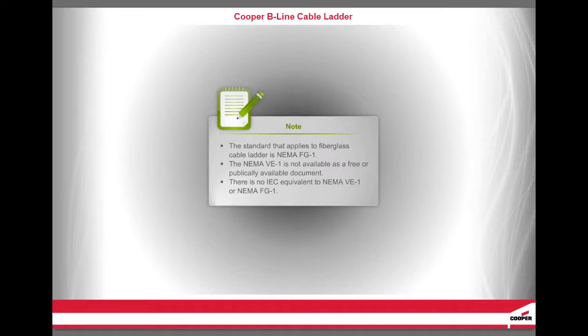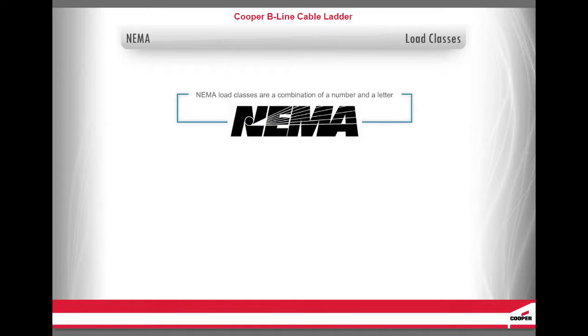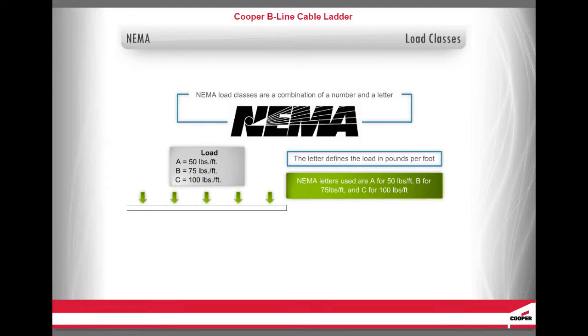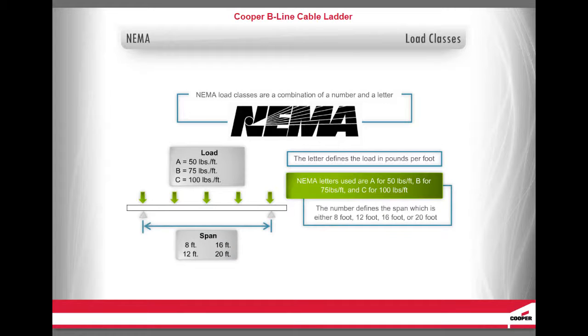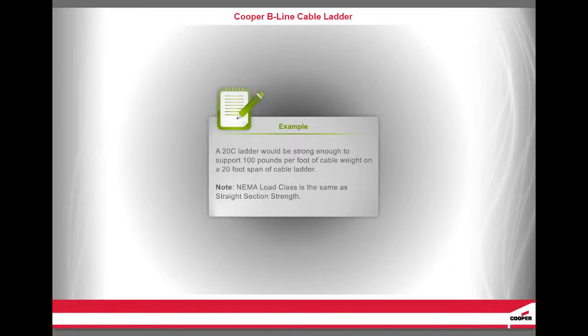The NEMA VE1 is not available as a free or publicly available document. There is no IEC equivalent to NEMA VE1 or NEMA FG-1. NEMA load classes are a combination of a number and a letter. The letter defines the load in pounds per foot: A for 50 pounds per foot, B for 75 pounds per foot, and C for 100 pounds per foot. The number defines the span — either 8-foot, 12-foot, 16-foot, or 20-foot. A 20C ladder would be strong enough to support 100 pounds per foot of cable weight on a 20-foot span of cable ladder.